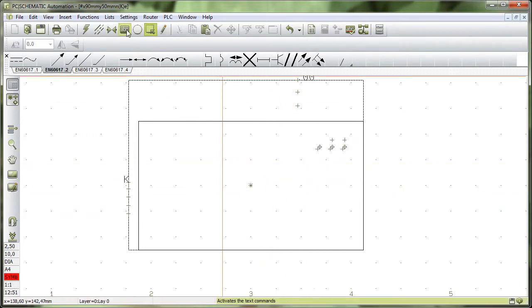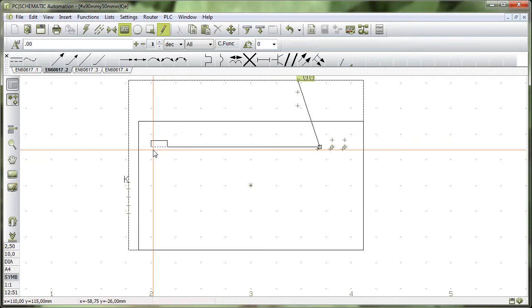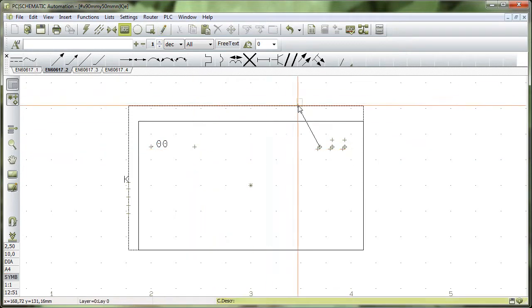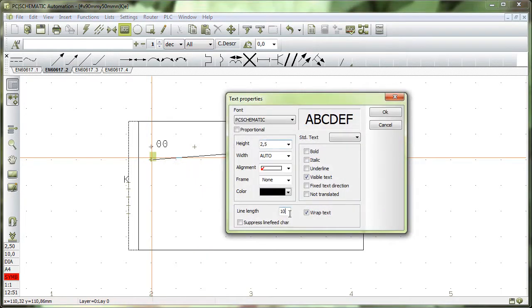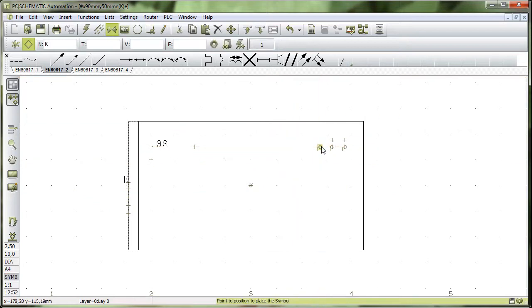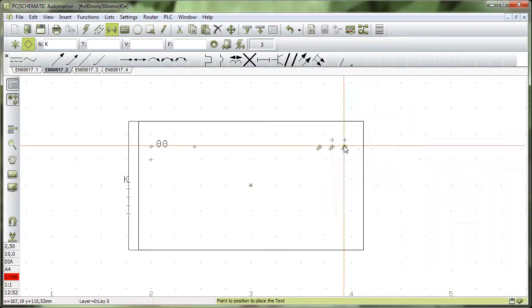I take all the text elements and place the address here, and the reference up above that. Below the reference I want the description for what is happening on this address. For the reference symbol, I may want 25 characters before wrapping the text, whereas in the PLC symbol I only want 10 characters. I check to make sure the address on all three connection points is dot zero zero — this will be the first of four addresses.